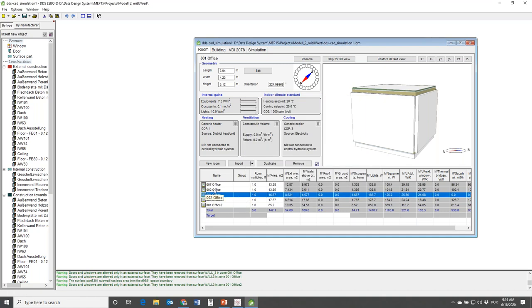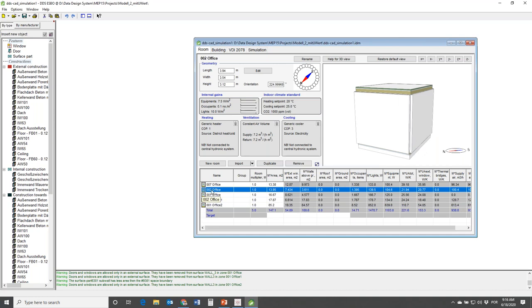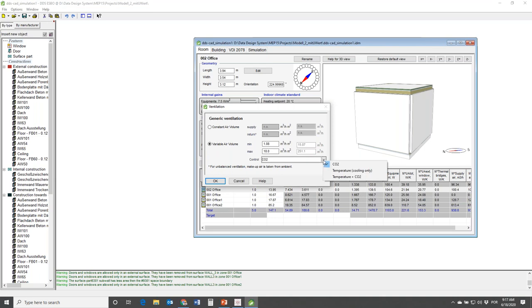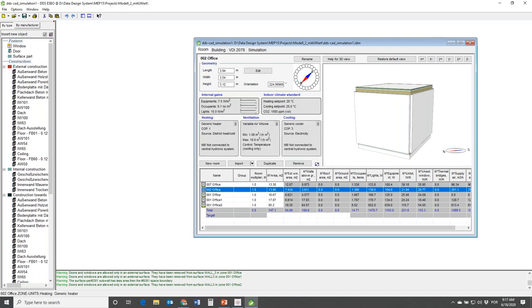Going to the other extreme - Room 002 - in terms of ventilation we want to use the VAV system we talked about earlier, and it's going to be temperature-controlled. Here we have a minimum value - the minimum ventilation rate that will always occur in the space - and a maximum value, the maximum ventilation rate the system can run when additional cooling is needed.